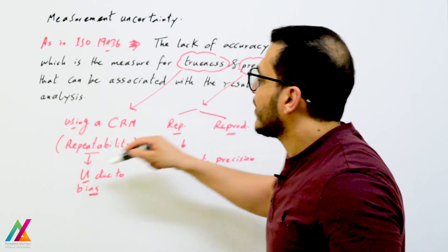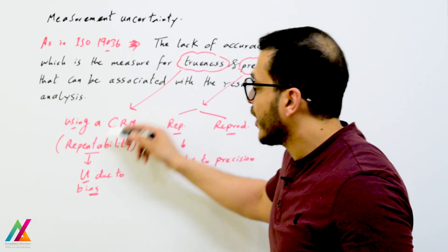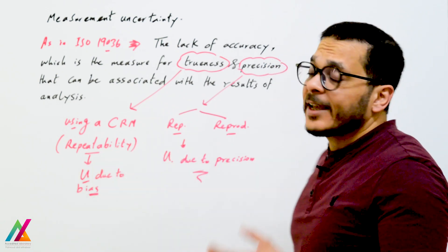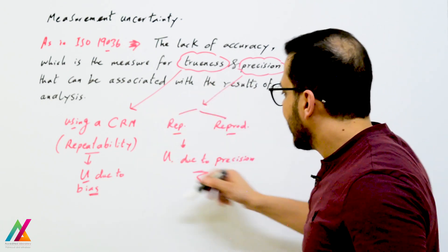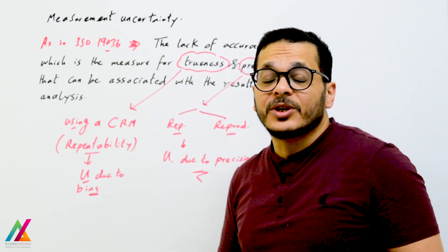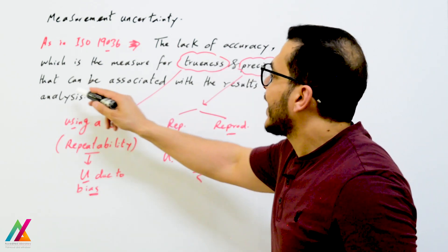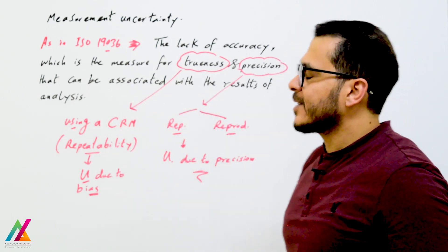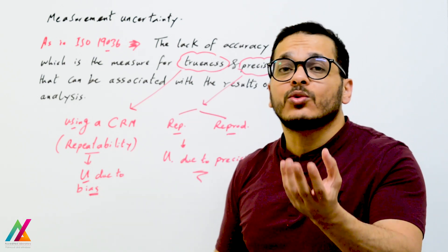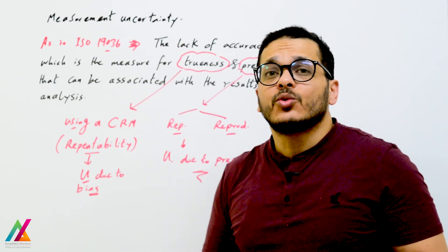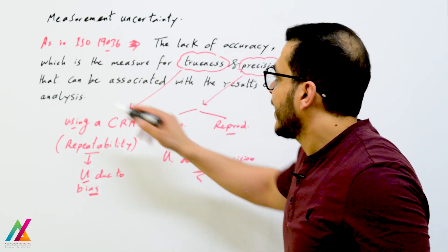Trueness is evaluated using certified reference material by making replicate analyses, then calculating uncertainty due to bias. Precision is estimated from repeatability and reproducibility, giving uncertainty due to precision. Altogether, the lack of accuracy associated with your analysis results — how much doubt exists in your measurement — is captured in the calculated uncertainty, which is then added to the final result.